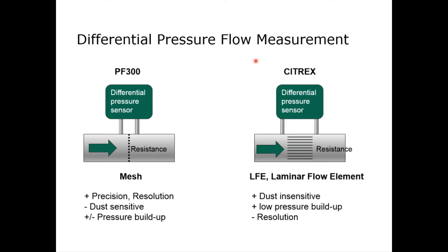Flow measurement, as we do it, is in general a differential pressure measurement via a resistance. So if the flow goes through this resistance, goes through the device, a differential pressure is built up and it is measured by the differential pressure sensor. This is the same in the Citrex as well as the PF300. The difference is what kind of resistance we are using.